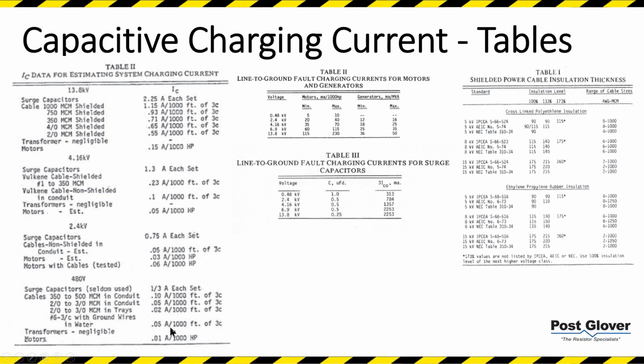And you can see here that there are much lower values for low voltage. The vast majority of the time at low voltage, you don't have to worry about this. It's still an issue, and we have the ability to measure in our system, which makes it a little bit easier. But the point is that 95 plus, or probably 98+% of the time, with some notable exceptions, probably data centers being one, you're going to have lower capacitive charging current. But as you get up higher, you have larger conductors, and you're going to have typically higher values at medium voltage. So you can have smaller systems and still have charging currents too high to meet the threshold of a high resistance ground. Just to mention again, with high resistance ground, you really want the ground fault current higher than the capacitive charging current.